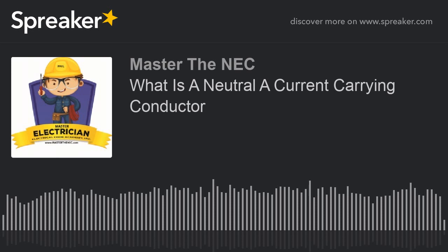Okay, so that's one of the aspects that we saw directly in C when you're dealing with the nonlinear loads, which can result in harmonic currents being present in the neutral conductor. Now, if that's the case, and again, we're dealing with a major portion of this, then the neutral conductor shall therefore be considered a current carrying conductor. And again, that's what brings in the adjustment factors in 310.15(B)(3)(a) if it needs to be applied if you have more than 3 current carrying conductors.